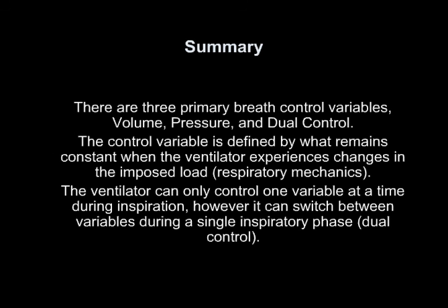In summary, there are three primary breath control variables: volume, pressure, and dual control. The control variable is defined by what remains constant when the ventilator experiences changes in the imposed load. The ventilator can only control one variable at a time during inspiration; however, it can switch between variables during a single inspiratory phase.